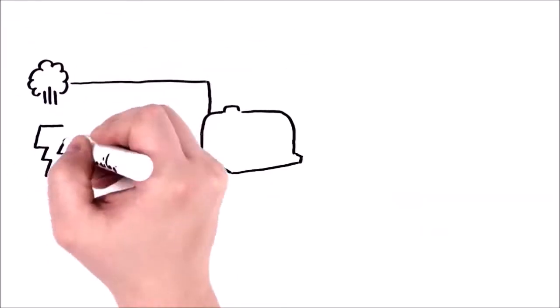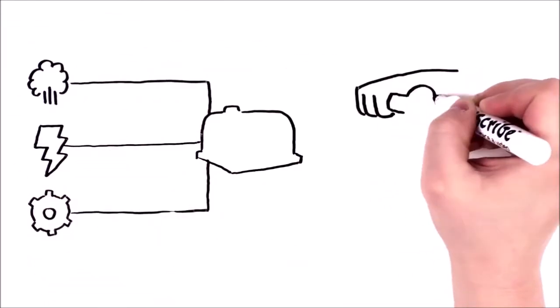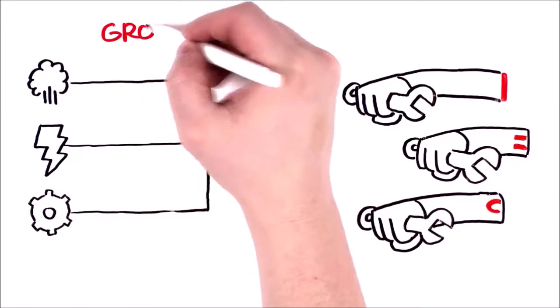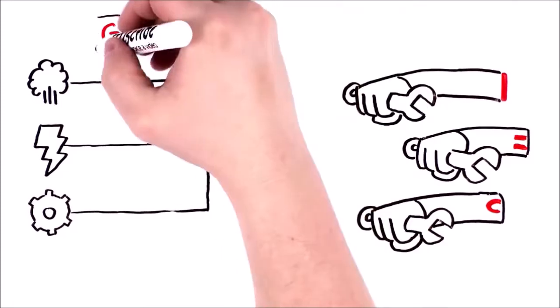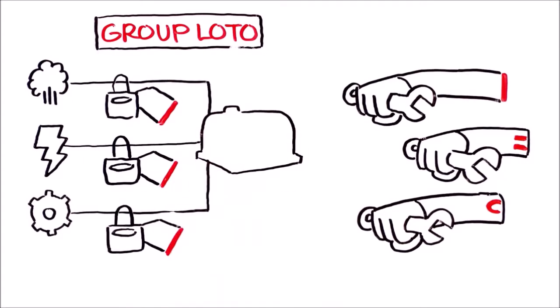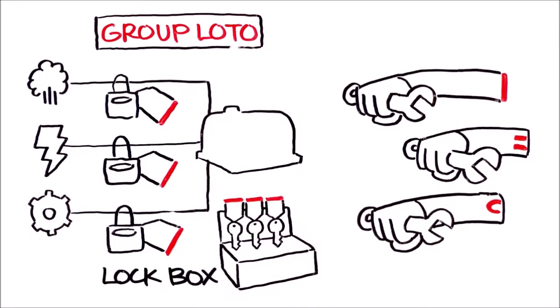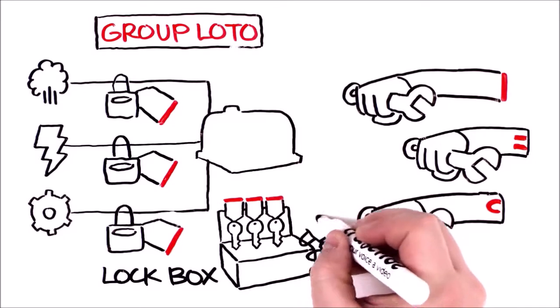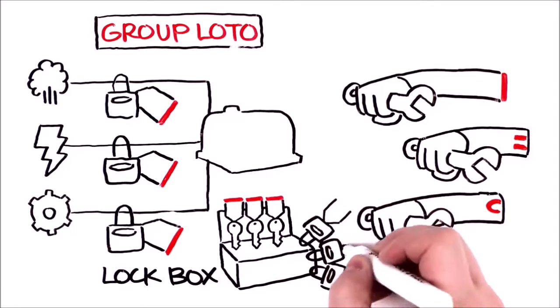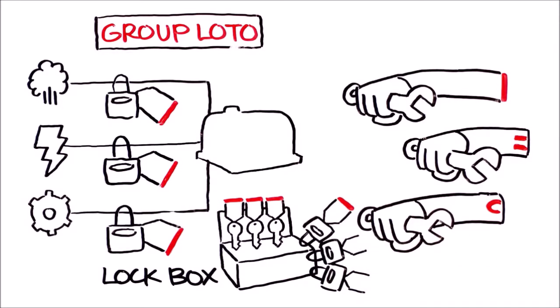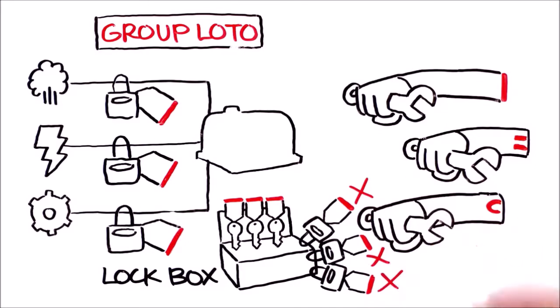What if the equipment has many energy sources, plus it's not just you? It's a group of people performing a service activity on the equipment. In this type of situation, group LOTO can be done. With group LOTO, it's typical to apply a different lock and tag to each energy source. Then place all the keys from these locks in a lockbox. Then all employees working on the equipment place their own lock on the lockbox while working on the equipment. But in these cases, each person must put their own lock on the energy isolation device. Under no circumstance is it ever acceptable for one person to lock out equipment for another.